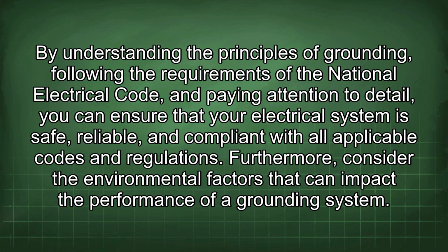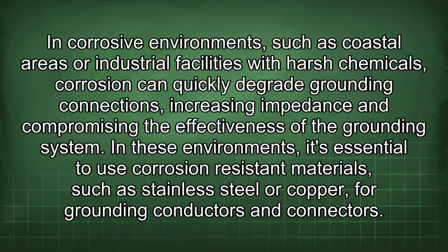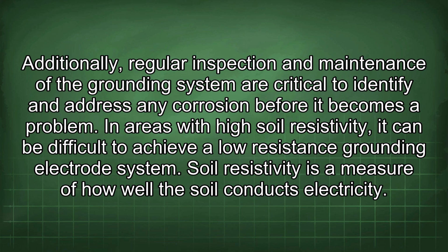Furthermore, consider the environmental factors that can impact the performance of a grounding system. In corrosive environments, such as coastal areas or industrial facilities with harsh chemicals, corrosion can quickly degrade grounding connections, increasing impedance and compromising the effectiveness of the grounding system. In these environments, it's essential to use corrosion-resistant materials such as stainless steel or copper for grounding conductors and connectors. Additionally, regular inspection and maintenance of the grounding system are critical to identify and address any corrosion before it becomes a problem.